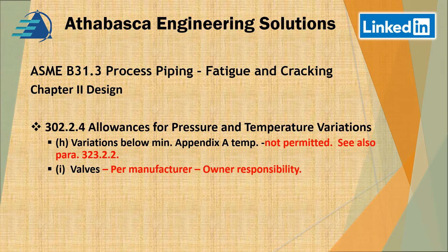Continuing through 302.2.4, section H states that variations below the minimum Appendix A temperature are not permitted. There are concerns about the brittle transition temperature, with more details found in 323.2.2. For valves, the onus is on the manufacturer for pressure variations, but it remains the owner's responsibility.